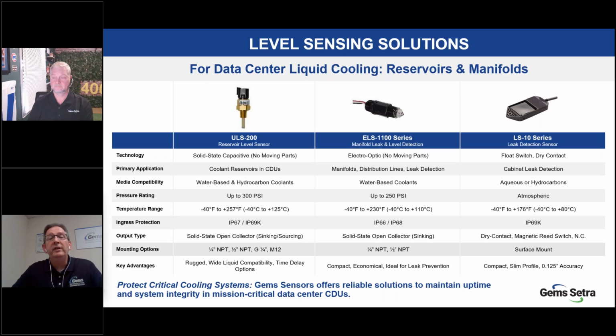Moving to the center is the ELS 1100. Again, a no moving part product, but instead of using capacitance, it's using light to determine if the liquid's there or not. Ideal for distribution lines and manifolds, coolants that are used throughout your applications. Again, ideally suited for that. But what's really nice is it's compact and fits in that profile, has a high pressure rating and temperature rating, has the IP ratings that you're probably looking for to protect the sensor, and a few mounting selections as well, so you can adapt that to your application. On the far right is our switch base.